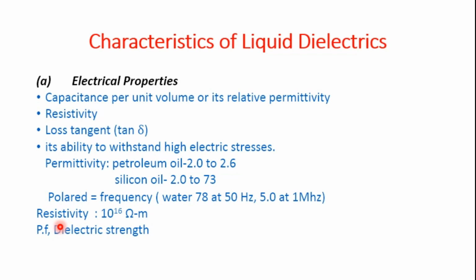Let's see that pure and dry transformer oil will have a very low power factor, varying around 10 to the power of minus 4 at 20 degrees Celsius and 10 to the power of minus 3 at 90 degrees Celsius at a frequency of 50 Hz. So there is a small change in the values. However, it is more important in the case of cables and capacitors.